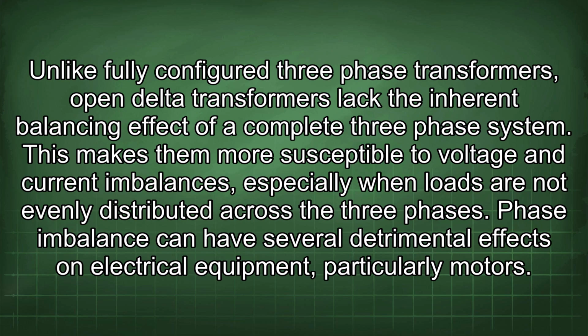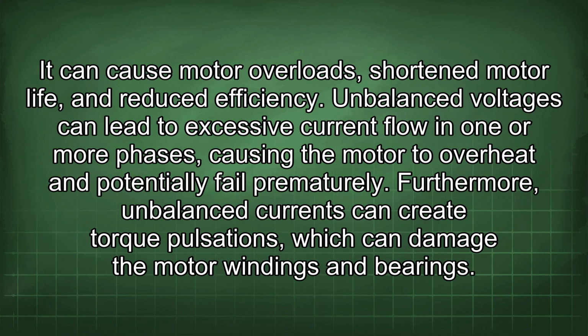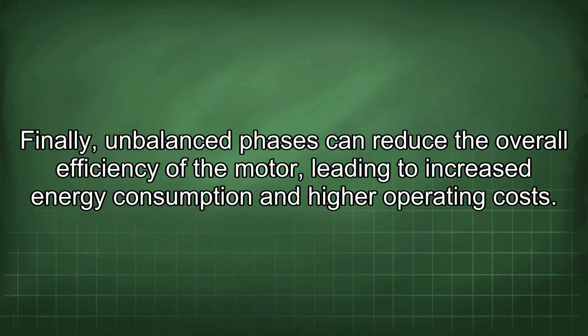Phase imbalance can have several detrimental effects on electrical equipment, particularly motors. It can cause motor overloads, shorten motor life, and reduce efficiency. Unbalanced voltages can lead to excessive current flow in one or more phases, causing the motor to overheat and potentially fail prematurely. Furthermore, unbalanced currents can create torque pulsations, which can damage the motor windings and bearings. Finally, unbalanced phases can reduce the overall efficiency of the motor, leading to increased energy consumption and higher operating costs.